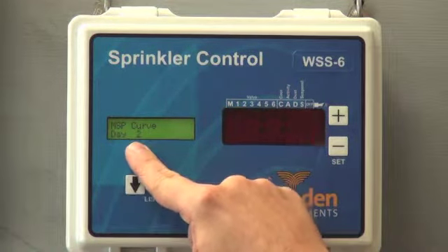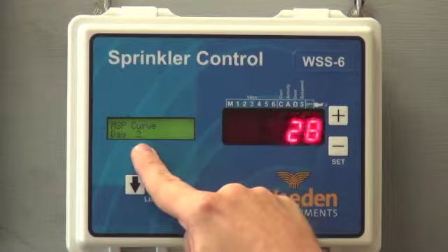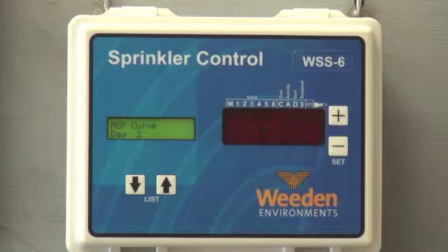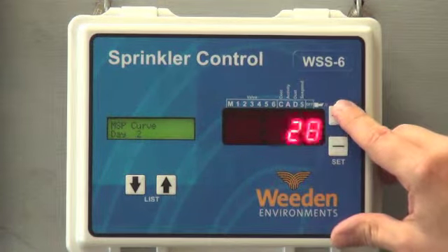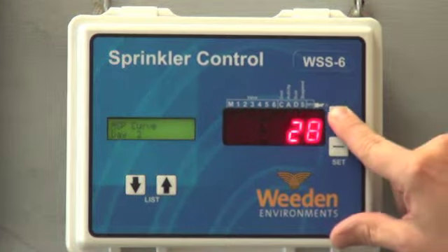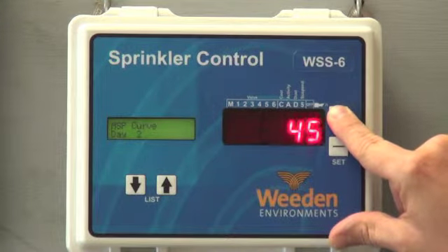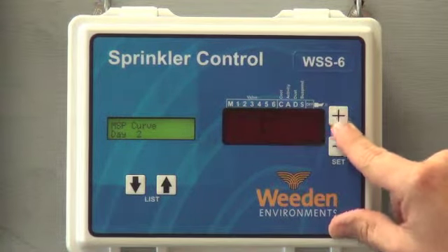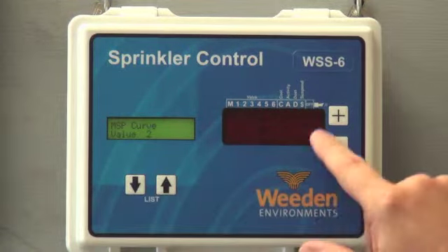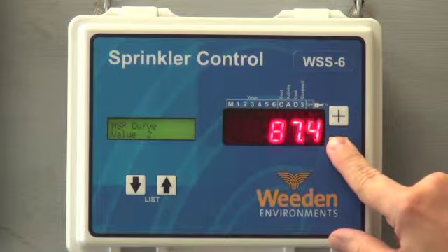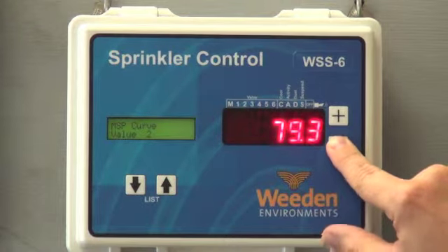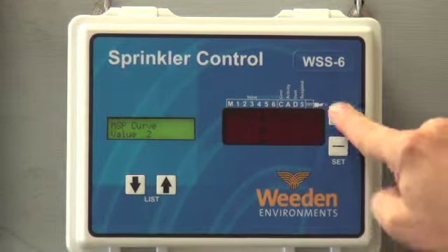Now we go to set point number 2, or MSP curve day 2. This one says 28 days, because this one's set up to do it every week. I told you there was 10 different set points, but let's make this a flock that is actually being grown to 60 days. So it's a heavy broiler flock. Let's change this to 56 days. What this means is that during the last week of the bird's life, from 56 days till market, that set point is showing 88 degrees here. Let's take that down to 78. There we go, 78 degrees.